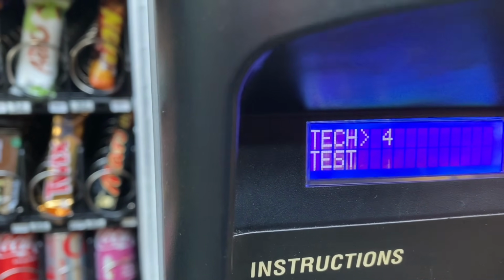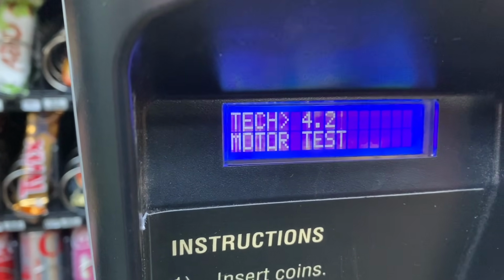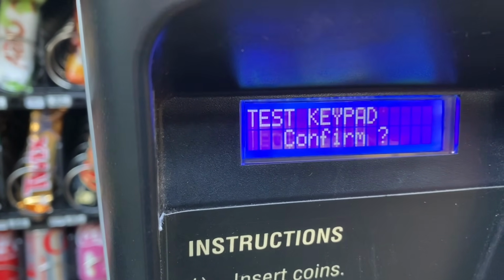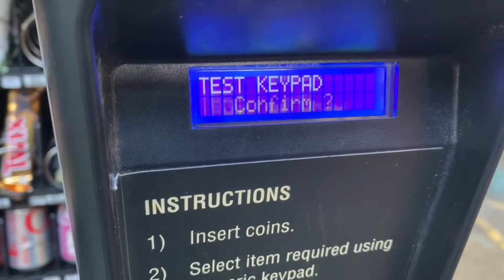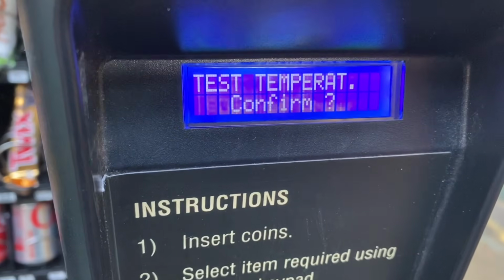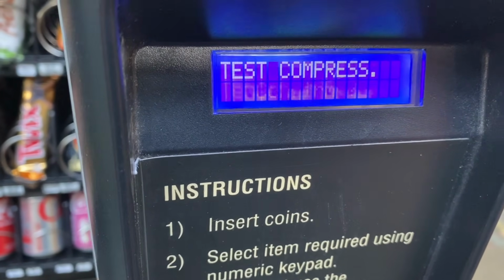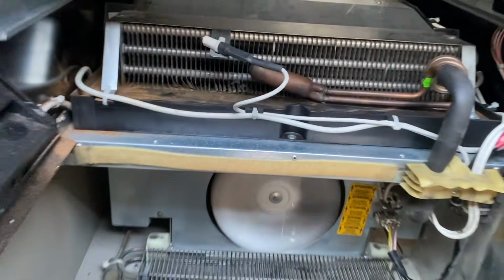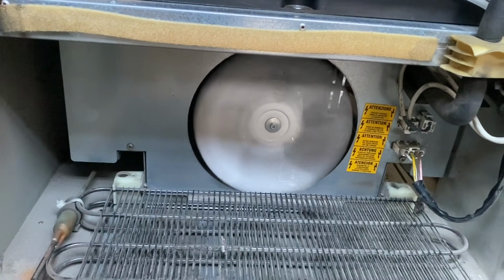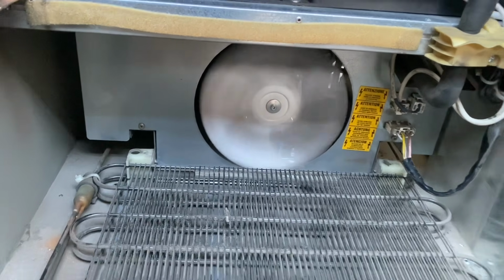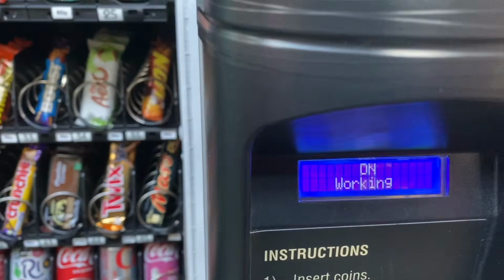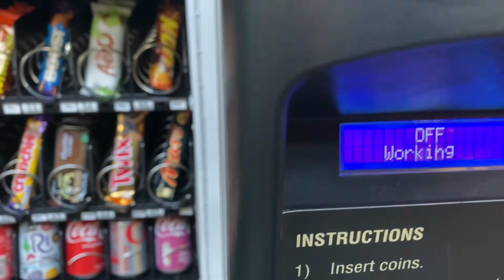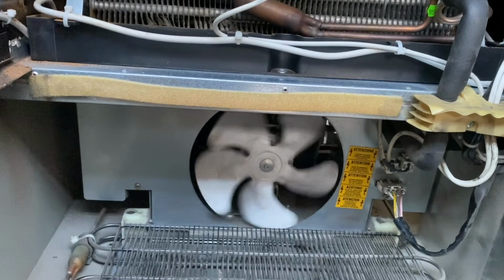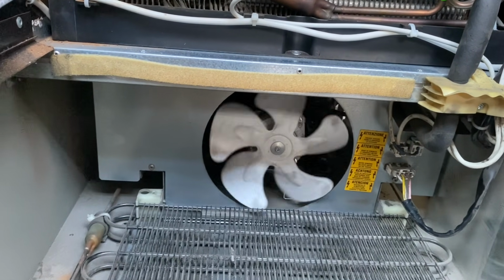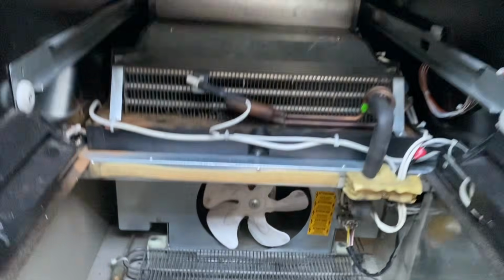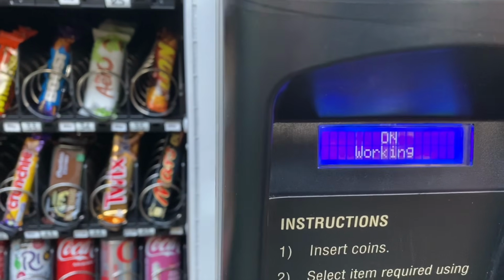And then if you go to the tech menu and go back to test, auto test, press enter, and then press C until you get to test compress. Once you're at test compress, press E to enter, and then that compressor should kick in and the fan motor should also turn. Now you can see there, successful swap of a fan motor, because that's now turning quite nicely and it sounds great. So we've done that. Turn it off in the program, it should then turn off. And just do this a couple of times just to make sure that the fan motor is kicking in when the compressor comes on as well. There we go.